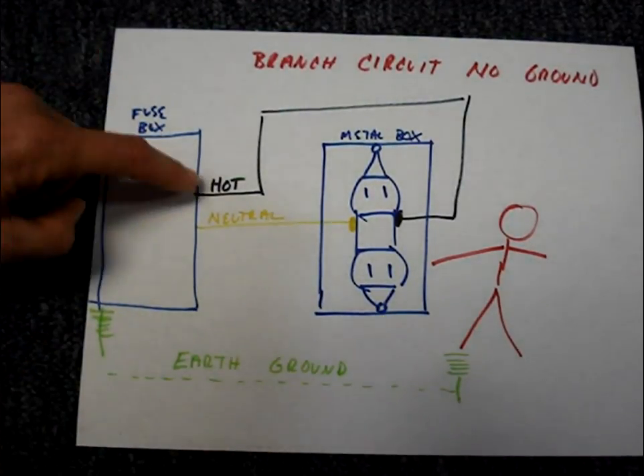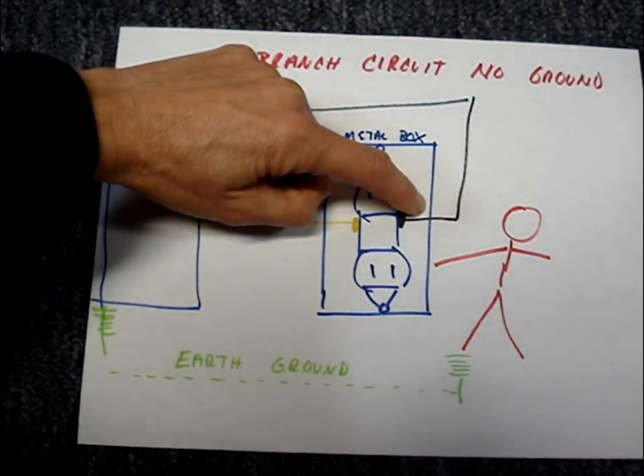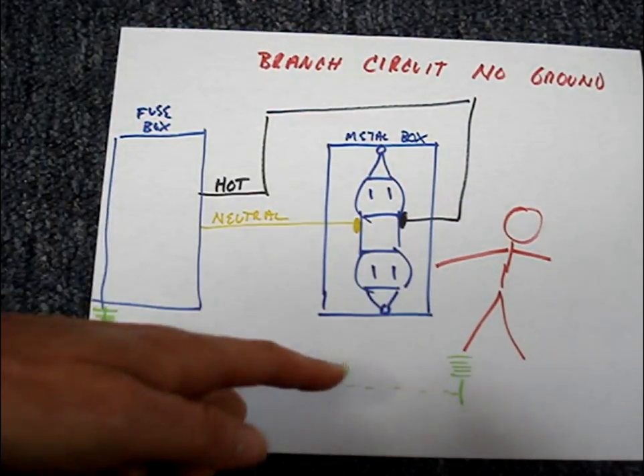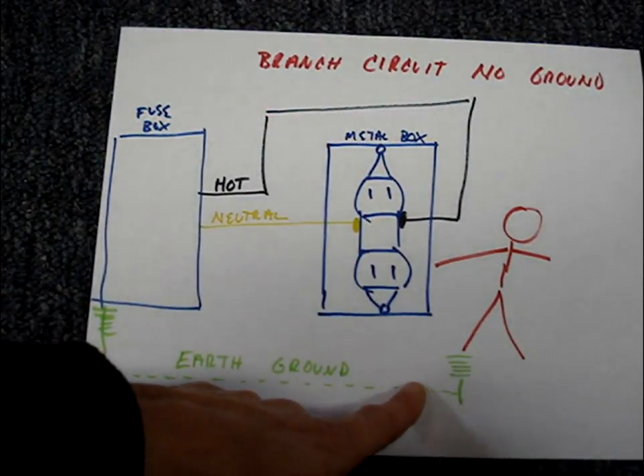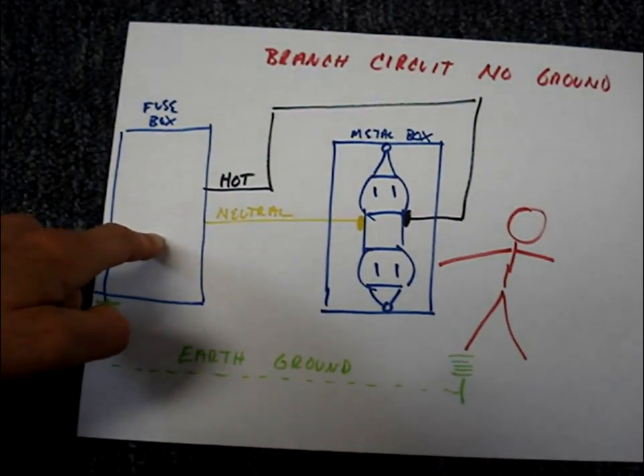The circuit would work this way: The current would flow through the hot onto the metal box, through the person, and then through the earth, which is now the big ground wire, and back up to the source.